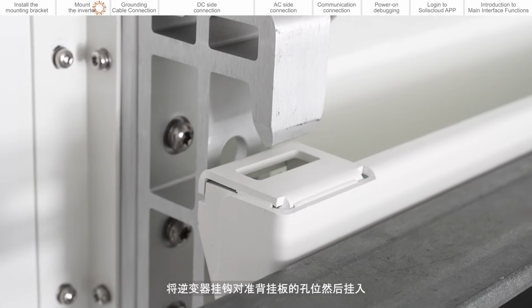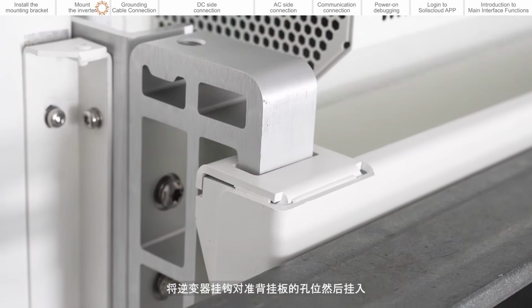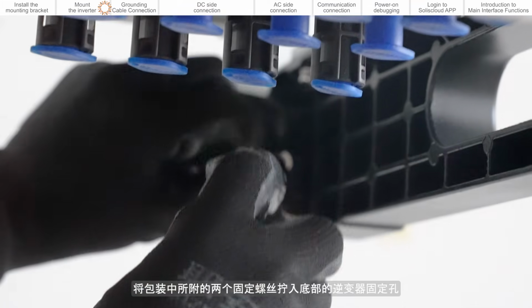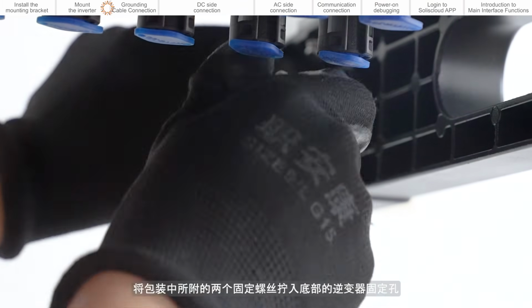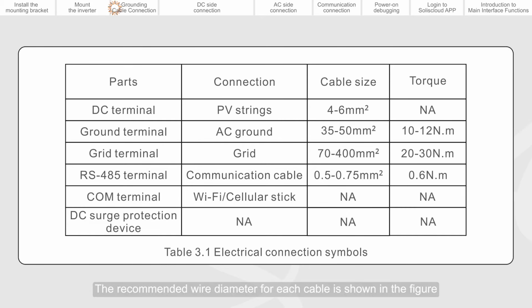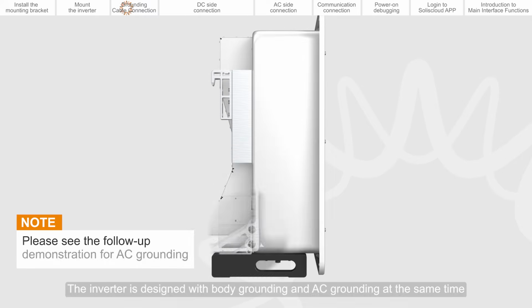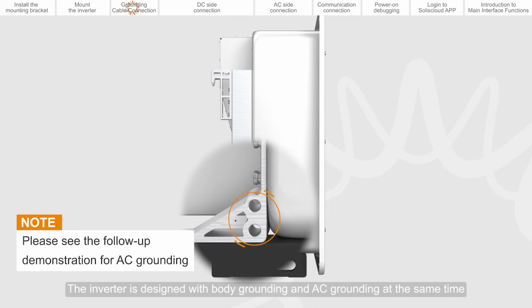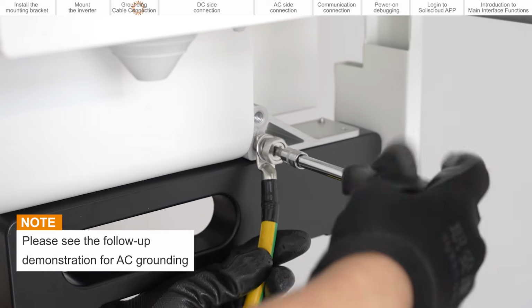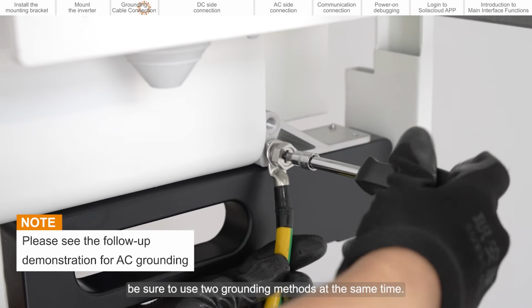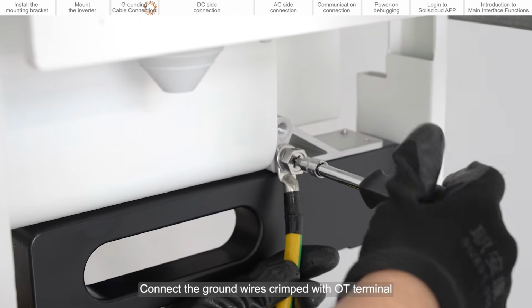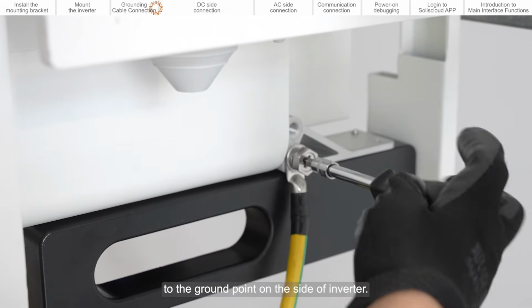Align the inverter hook with the hole of the back hanging plate, and then hang it in. Screw the 2 fixing screws included in the package into the inverter fixing holes at the bottom. Grounding cable connection. The recommended wire diameter for each cable is shown in the figure. The inverter is designed with body grounding and AC grounding at the same time. To ensure safety, be sure to use 2 grounding methods at the same time. Connect the ground wires crimped with OT terminal to the ground point on the side of the inverter.